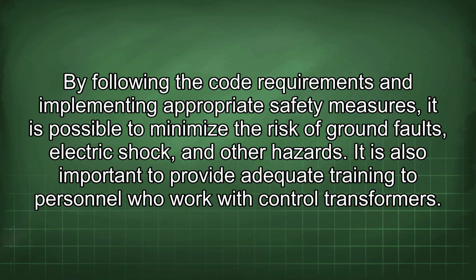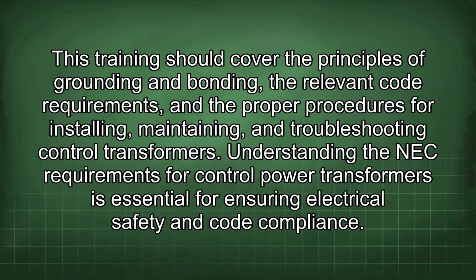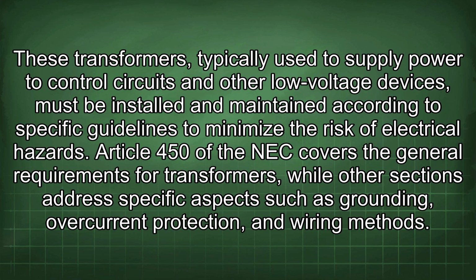It is also important to provide adequate training to personnel who work with control transformers. This training should cover the principles of grounding and bonding, the relevant code requirements, and the proper procedures for installing, maintaining, and troubleshooting control transformers. Understanding the NEC requirements for control power transformers is essential for ensuring electrical safety and code compliance. These transformers, typically used to supply power to control circuits and other low-voltage devices, must be installed and maintained according to specific guidelines to minimize the risk of electrical hazards.